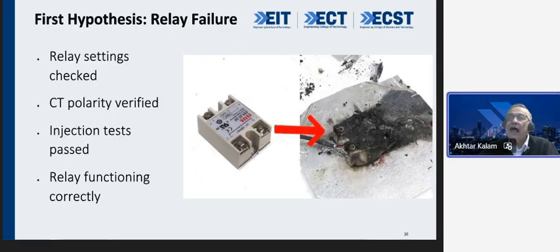Therefore, as Inspector Jacques Clouseau, I come to some sort of hypothesis. And the first thing I do: the relay is the failure. The brain, which is the relay, is a failure. So I do the setting check. Then I looked at the polarity of the CTs. I did some injection tests. It passed. I looked at the relay. The relay is functioning properly.